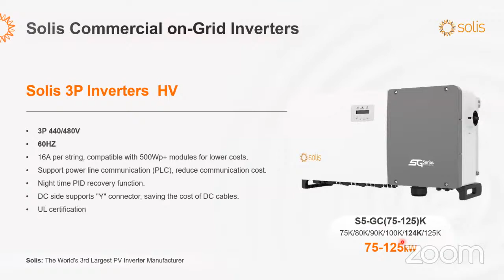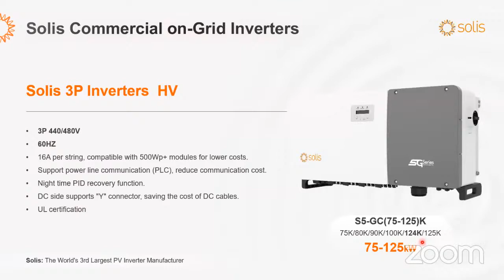From 75 to 100, you have also the possibility to add a rapid shutdown device. So the inverters can be ordered with the rapid shutdown controller inside the inverter, and you will only need to add the rapid shutdown device on the panels. Of course, as mentioned, depending on your requirements, please come to us, please come to Mako, please state your requirements, your needs, the project details, and we will try to come up with the most suitable solution for your project. These inverters are UL certified, as mentioned, and they only work at 60 hertz. We do have a product line that comes in 80, 100, and 110 in IEC and three-phase 380. But yeah, we can mention that later on.